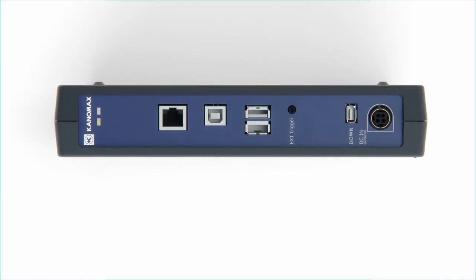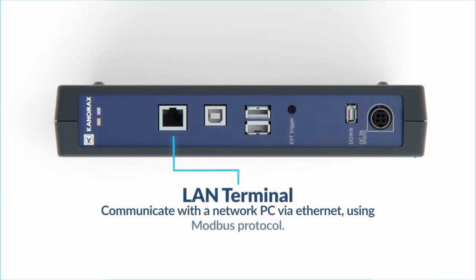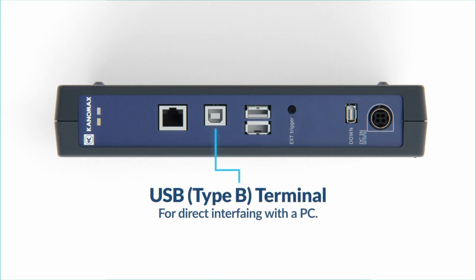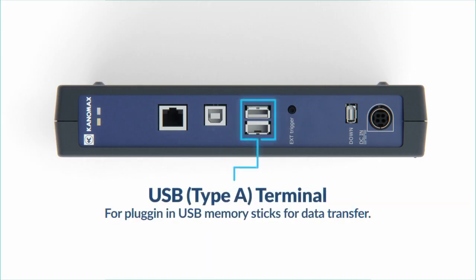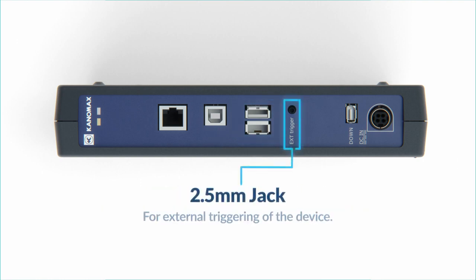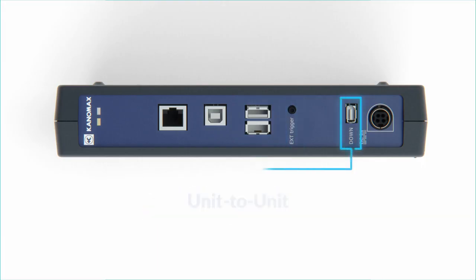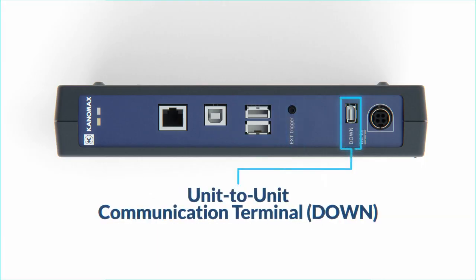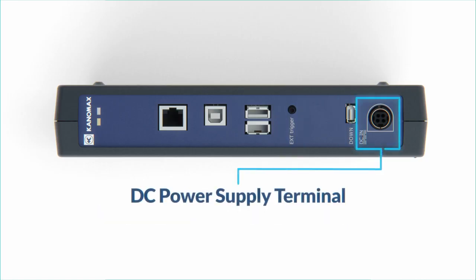On the top of the 1590's main unit, there are a number of useful terminals to work with. The LAN terminal is used for communicating with a network PC via Ethernet using Modbus protocol. The USB Type-B terminal is used for direct interfacing with a PC, and the USB Type-A terminal is used for plugging in USB memory sticks for data transfer. Next to that is a 2.5mm jack for external triggering the device. The last 2 ports are a unit-to-unit communication terminal and a DC power supply terminal.